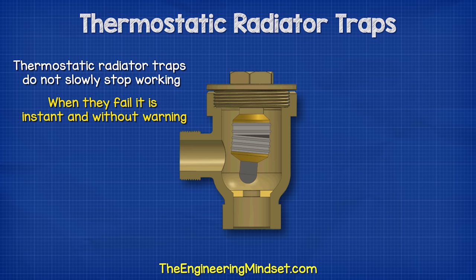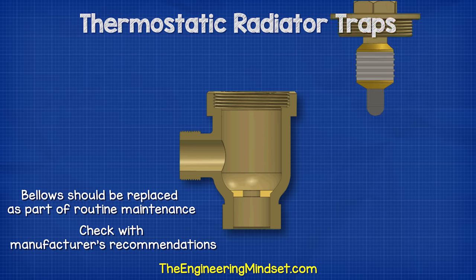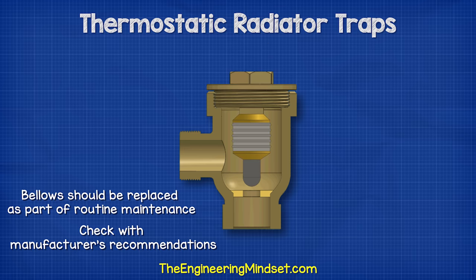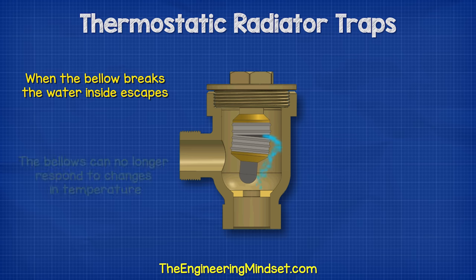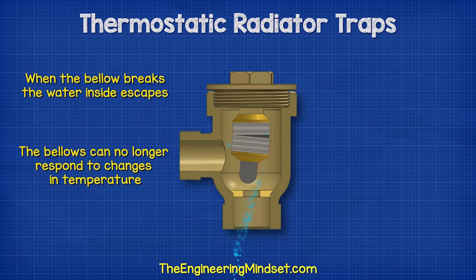Thermostatic radiator traps do not slowly stop working — when they fail, it is instant and without warning, with no slow deterioration in operation. Therefore, bellows should be replaced as part of routine maintenance according to the manufacturer's recommendations. When the bellow breaks, the water inside escapes and the bellow can no longer respond to changes in temperature.